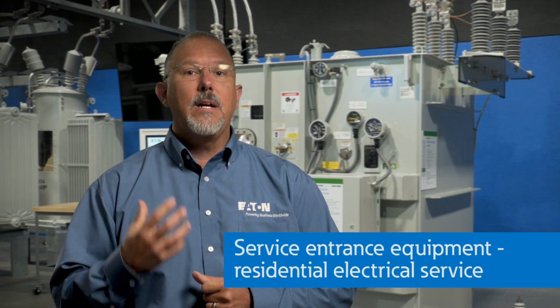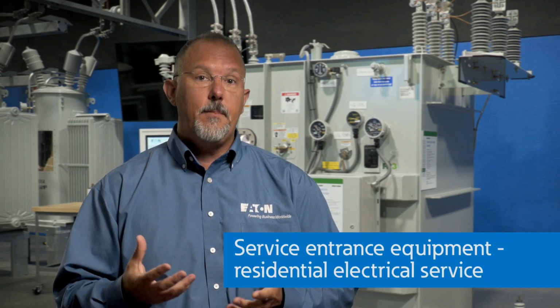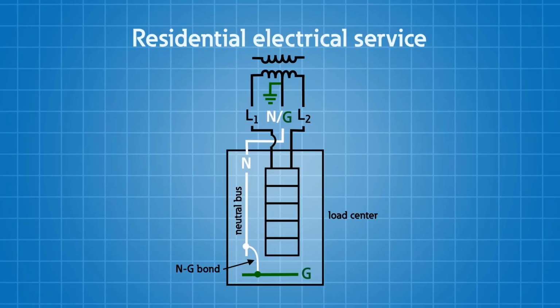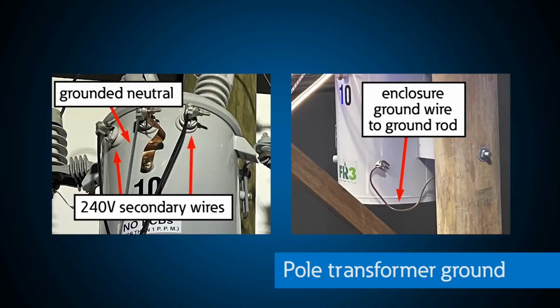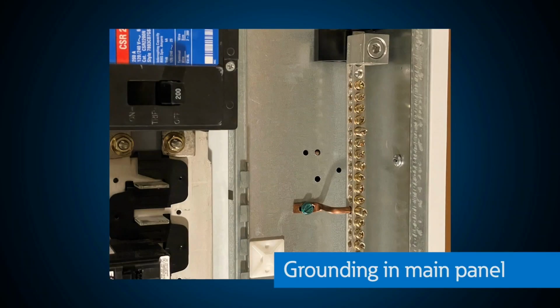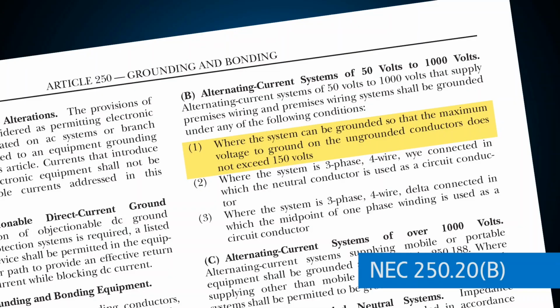Let's show you how a residential service and a load center are typically grounded and bonded. A residential system is a solidly grounded system with 2 hots and a grounded neutral conductor, which is a single wire. This allows the utility to ground the transformer and you to ground your main load center without dividing the current going back to the source because there's only 1 wire. NEC section 250.20(B) tells us that all premises wiring systems shall be grounded when the voltage to ground on the ungrounded conductors doesn't exceed 150 volts.